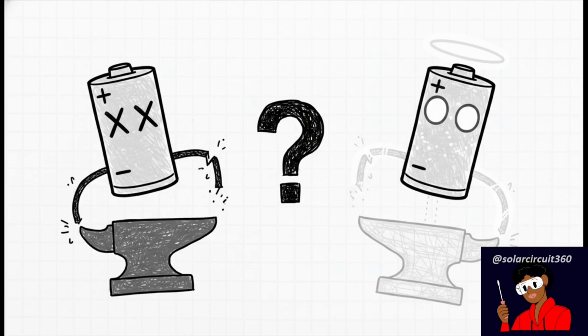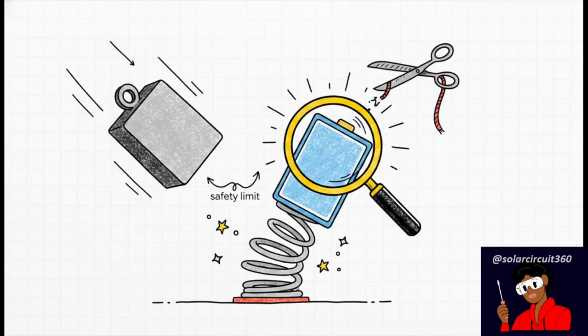Which leads perfectly into a scenario that absolutely drives battery owners up the wall. I like to call it the BMS mystery. Picture this. Your inverter is pulling a massive load, and suddenly, bam, the battery shuts off completely. Everything is dark. But then, maybe a few moments later, for seemingly zero reason at all, the battery wakes back up and everything looks perfectly fine. So, what on earth just happened? Well, the mystery is solved when you understand voltage recovery.